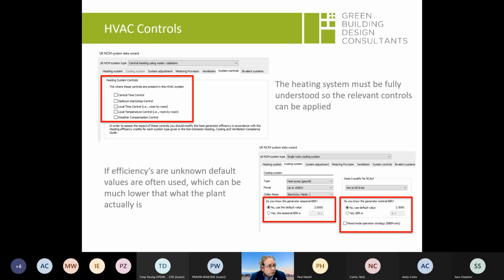The important thing is that if the efficiencies of the central plant aren't sought by the EPC assessor and inputted, it will use default settings, which typically for generators and chillers is between 2 and 2.5. Most modern chillers are much higher than 2, and split air conditioning or VRF type systems are considerably better than 2.5—depending on how it's run, some good systems can run at 5 to 1, meaning 1 kilowatt of electrical energy in and 5 kilowatts of heat or cooling energy out.